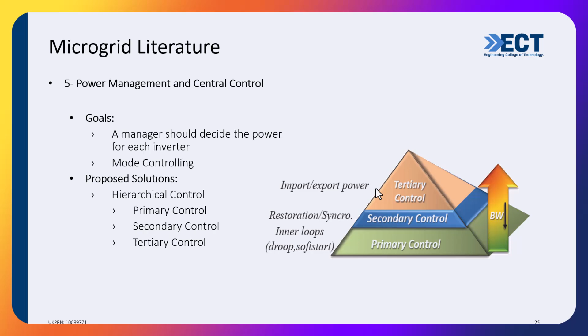The management of a microgrid is not really one layer of management, but we have 3 layers. The primary control, where each customer has control of the active and reactive power. We also have secondary control, where we restore the voltage and the frequency to help the grid. And we have the third layer, the supervisory control, where we establish, for example, an energy management system for the night and the day, deciding which unit should provide more or less power, and that dictates the prediction as well, and load shedding. If we don't have any more power and we have to shed some loads, turn off some loads, that's the responsibility of this control. So we have 3 levels of controllers. One level can be controlled by the customers, and the others should be controlled by the grid operator.